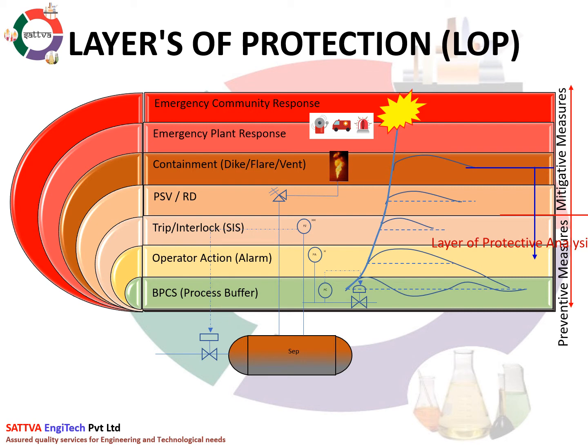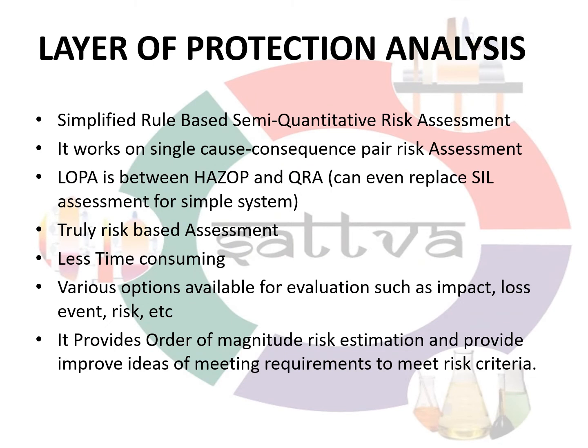There are a few basic requirements for meeting LOPA — layers must be independent, reliable and auditable. LOPA is a simplified rule-based semi-quantitative risk assessment; it works on a single cause-consequence pair risk assessment. LOPA sits between HAZOP and QRA, or can even replace SIL assessment for simple systems.